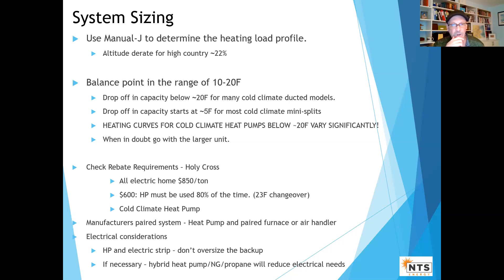The reason to size up is: with the turndown, you're really not using much energy in mild temperatures, but it makes a big difference keeping propane or electrical backup use down. Check the rebate requirements — Holy Cross has certain ones, Xcel has certain ones, tri-state co-ops have certain requirements — and make sure the equipment matches the specs. Manufacturer paired system requirements usually apply.